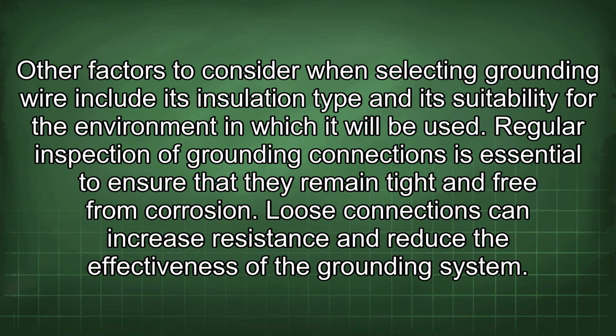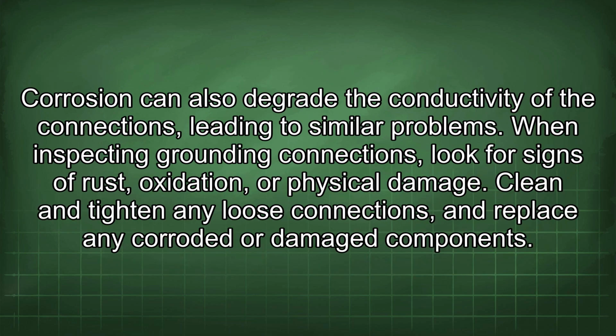Other factors to consider when selecting grounding wire include its insulation type and its suitability for the environment in which it will be used. Regular inspection of grounding connections is essential to ensure that they remain tight and free from corrosion. Loose connections can increase resistance and reduce the effectiveness of the grounding system. Corrosion can also degrade the conductivity of the connections, leading to similar problems. When inspecting grounding connections, look for signs of rust, oxidation, or physical damage. Clean and tighten any loose connections and replace any corroded or damaged components.